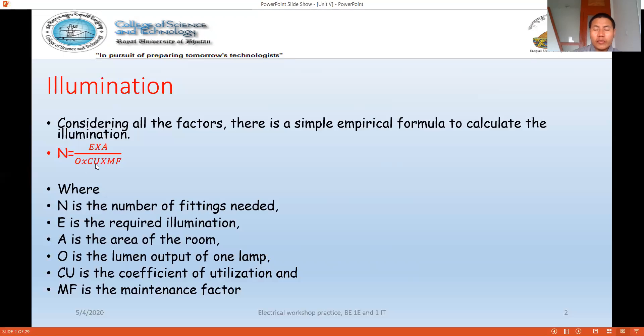The formula is: N = (E × A) / (Φ × CU × MF), where N is the number of required lamps or lighting points. E is the required illumination in lux, A is the area of the room, Φ is the lumen output of one lamp, CU is the coefficient of utilization, and MF is the maintenance factor.